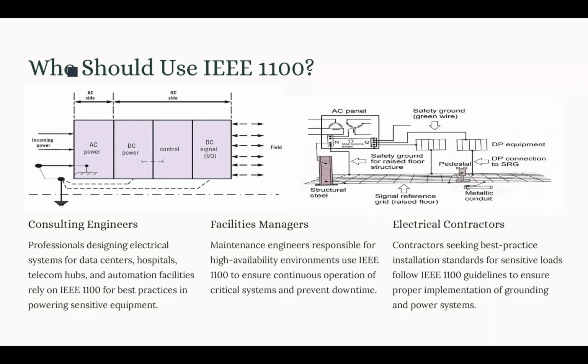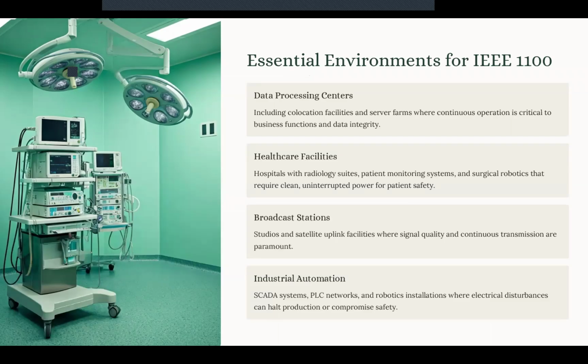Now, improper practice done by a contractor, like bonding ground at multiple points or sharing a neutral conductor, can basically nullify the entire functional grounding strategy and lead to logic faults or equipment damage. Now, there are some essential environments that IEEE 1100 would support and cover.